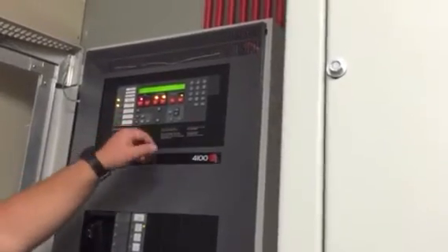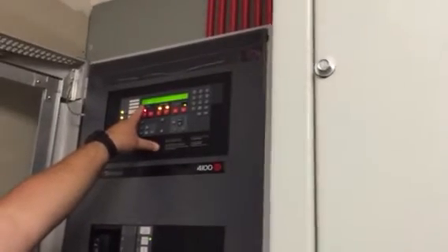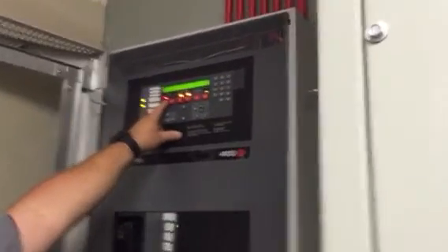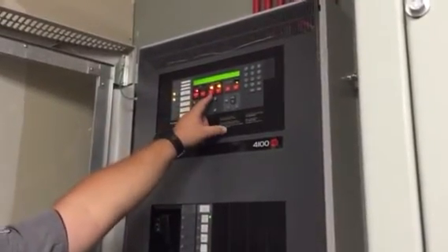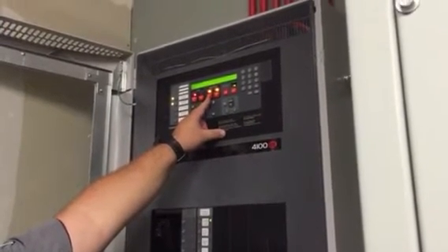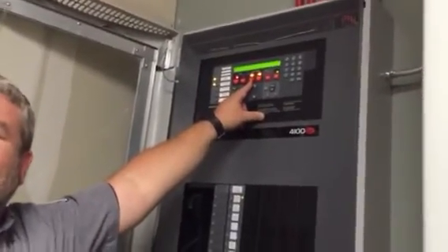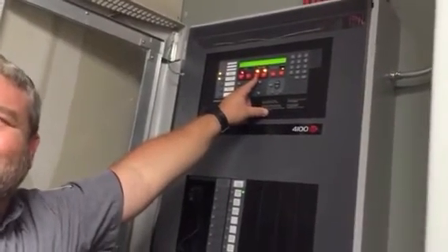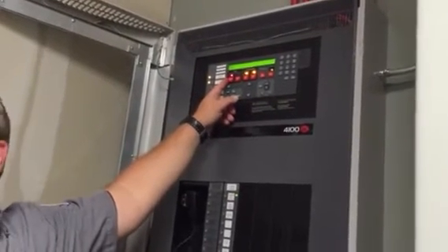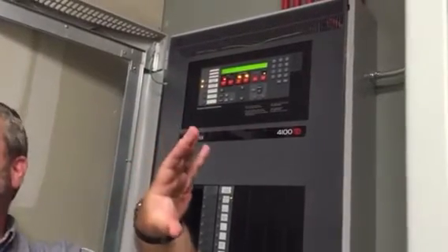Gotcha. So it'll come up and it'll tell you where it's at and what it is. That was a pull station. Smoke detector will come up and say smoke. Duct detector would be duct detector. Actually, your duct detectors in the building on the air handlers will come in as a supervisory. They will not come in as an alarm. A lot of times those are set up so if there's work being done and the dust gets sucked up into the air handler, you're not dumping the building. So once the alarm comes in, you go and you verify nothing's going on there, everything's fine. Of course, the alarm's going to go off at that same time.